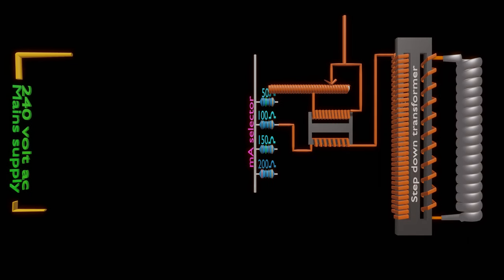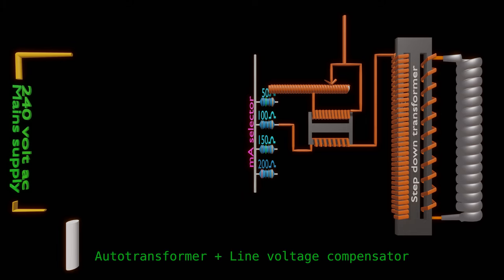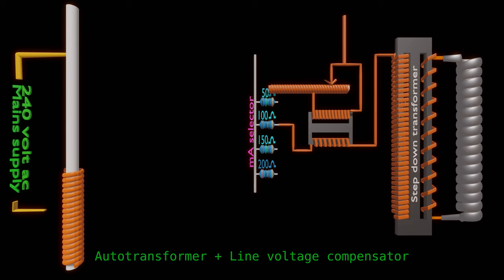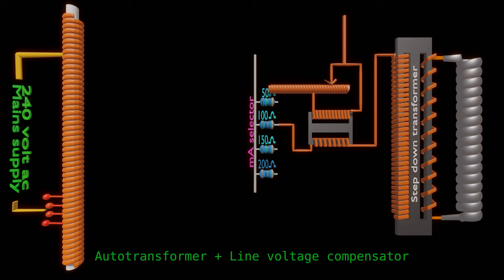An unnecessary change or fluctuation in filament voltage can cause similar changes in X-ray tube current. Hence, voltage stabilization in an MA circuit is very important. Fluctuations in mains supply is stabilized by using an autotransformer along with line voltage compensator. Line voltage compensator can only manage voltage fluctuations in mains supply. It cannot deal voltage fluctuations due to exposure.